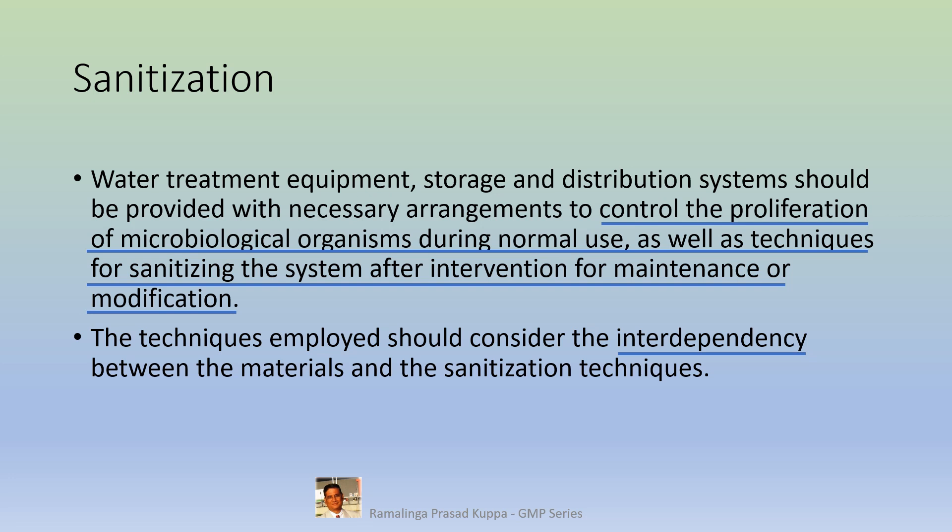For example, for microbial control, chlorine is dosed into the input water for purification. Unless the chlorine is neutralized to less than 0.5 ppm, the RO membranes get damaged.